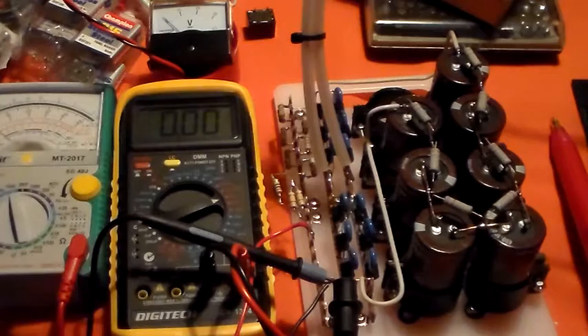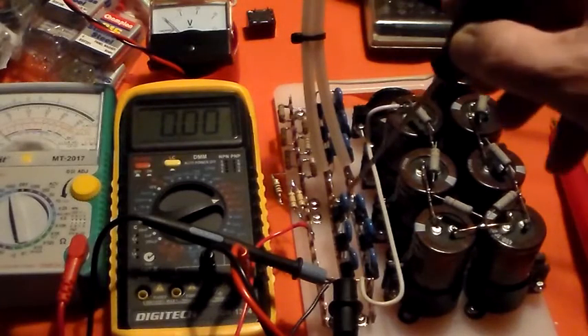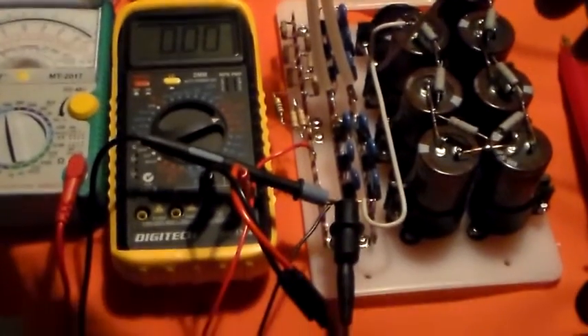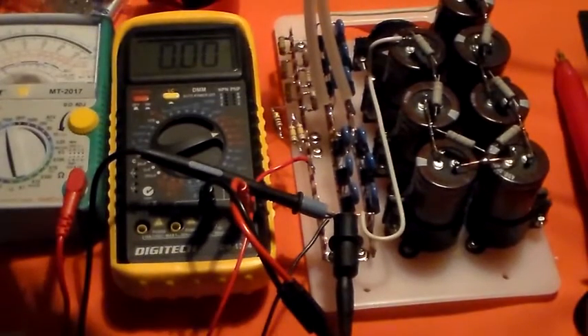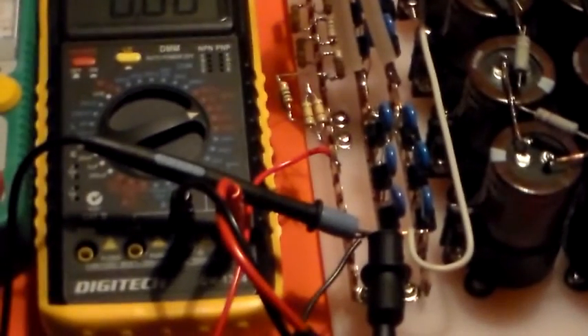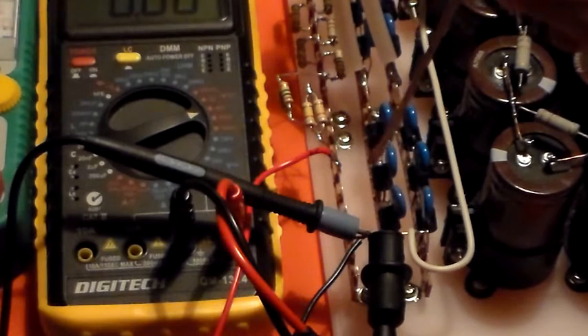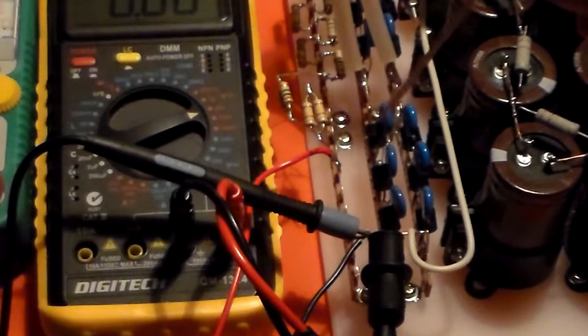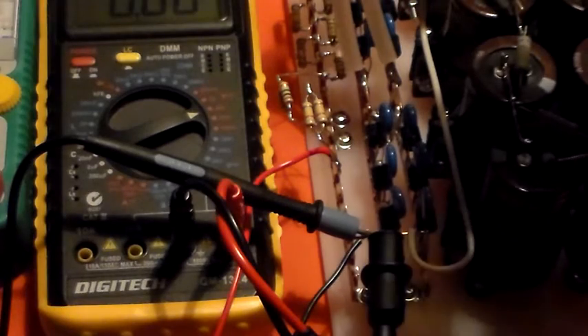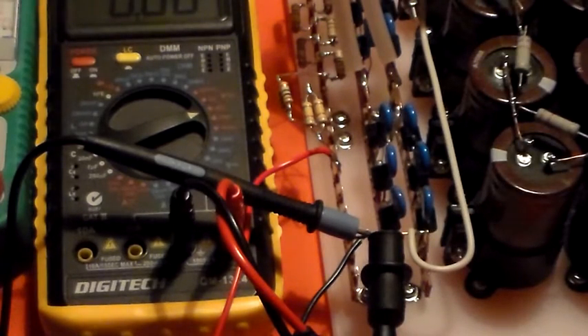Now these are the rectifiers down here - let me zoom in on that a bit. These are 1000 volt, 6 amp rectifiers. Each one's got a 0.01 capacitor rated at 3000 volts across it. This is the bottom half of the bridge, and there's an identical arrangement up here on the top half.